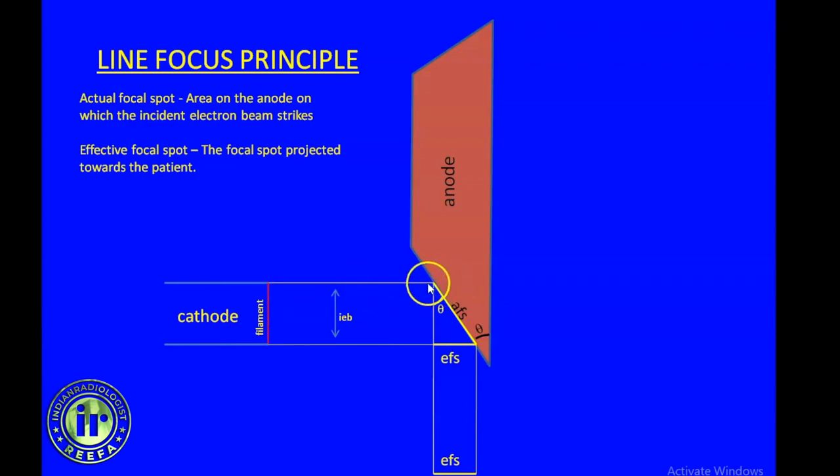As this electron beam strikes the anode, we can achieve a narrow electron beam by having a shorter filament. But more heat will be concentrated on a smaller area of the anode. X-ray production releases tremendous heat energy. In fact, 99% of the energy is lost as heat, and only 1% is fruitful in the production of x-ray. This high energy beam converging on a smaller surface area results in poor heat dissipation and reduced life of the x-ray tube.